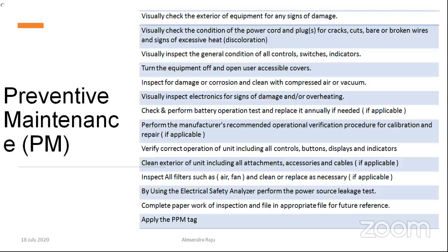And then comes we can verify the operations like buttons, display, and indicators. Another thing is that we can clean the exterior of the unit, including the accessories and cables. We can clean it and use it properly.